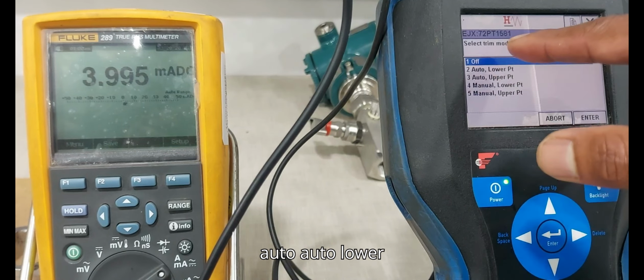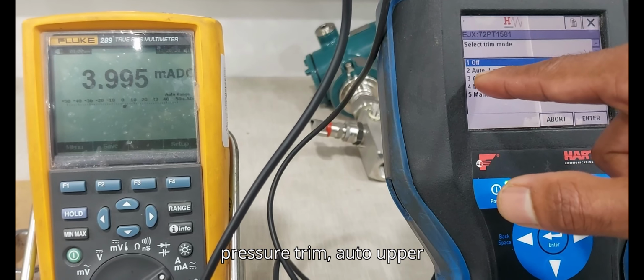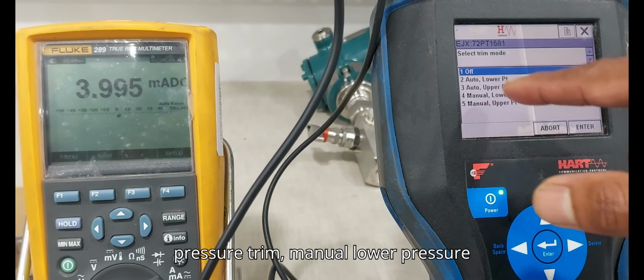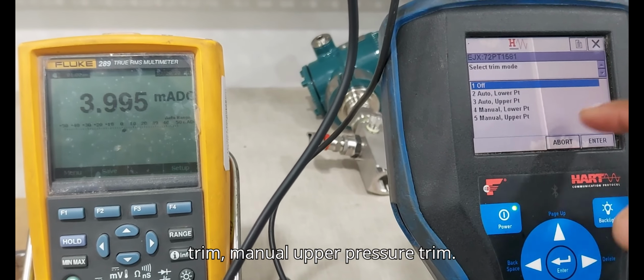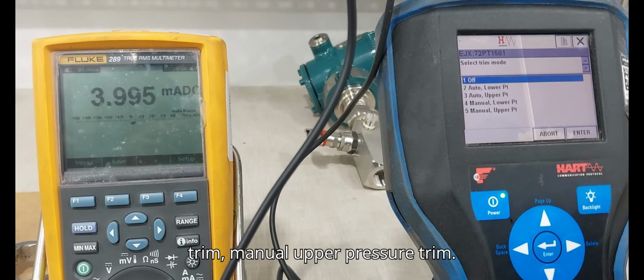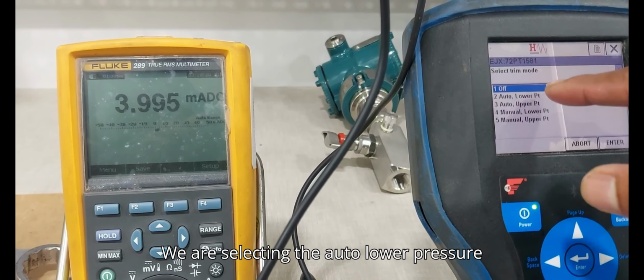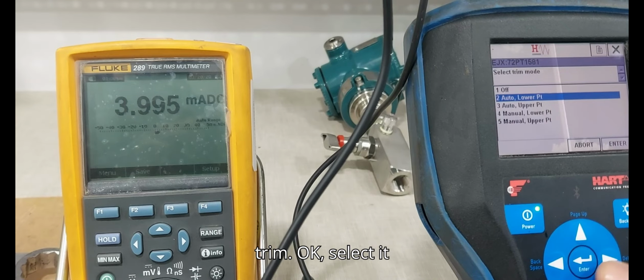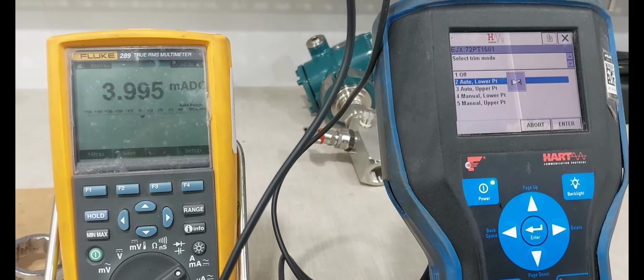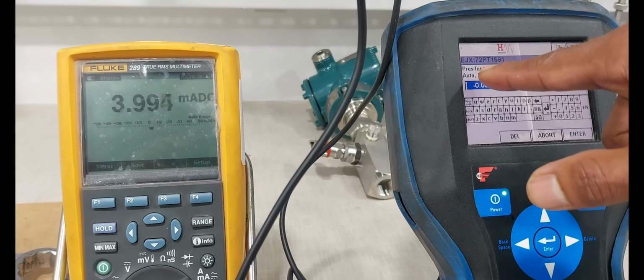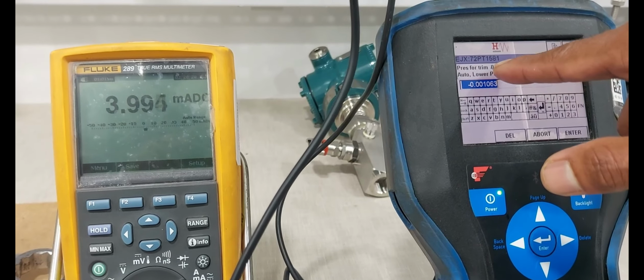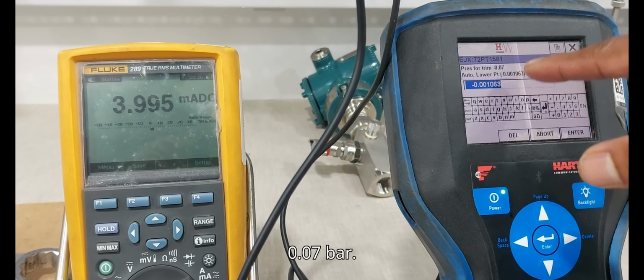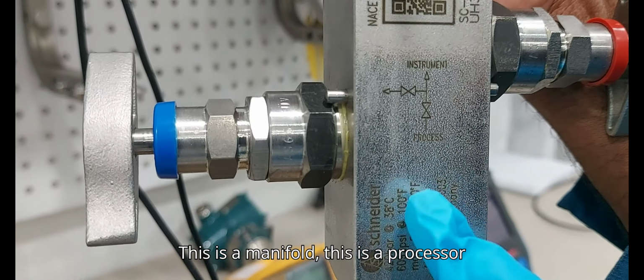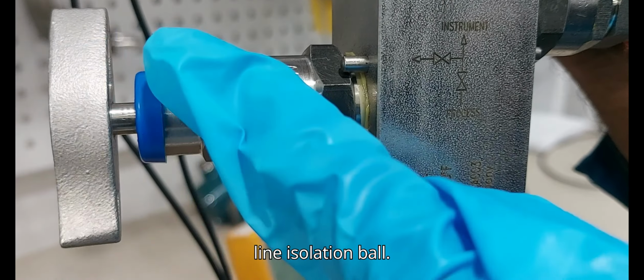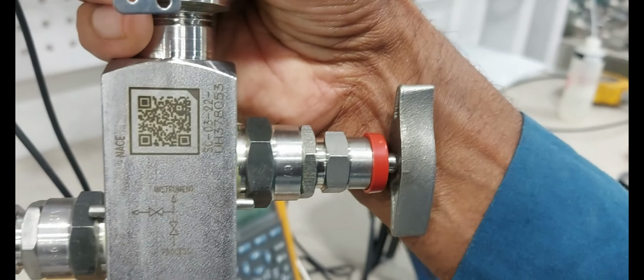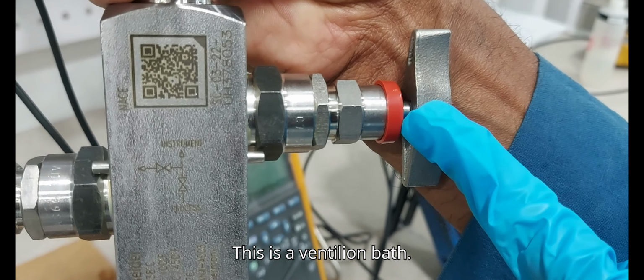Auto lower pressure trim, auto upper pressure trim, manual lower pressure trim, manual upper pressure trim. We are selecting the auto lower pressure trim. Okay, select it. Pressure trim is now showing 0.07 bar. This is the manifold. This is the process line isolation valve. This is the vent line valve.